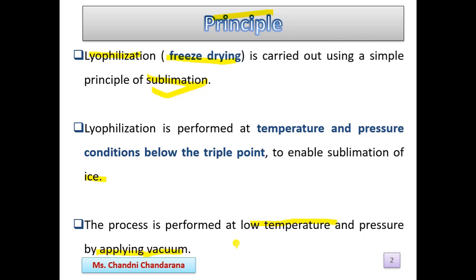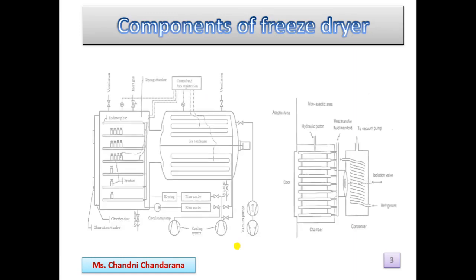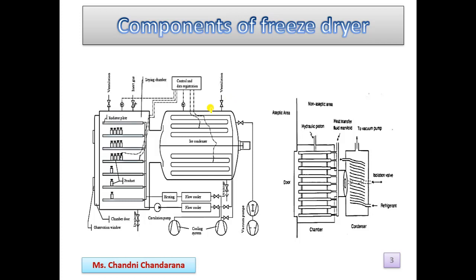The components of a freeze dryer (lyophilizer) include: a drying chamber, a vacuum pump, a cooling system, an ice condenser, and electric coils. The process is carried out in an aseptic area, while certain components such as the condenser and vacuum pump are in the non-aseptic area. A refrigerant is also part of the system.